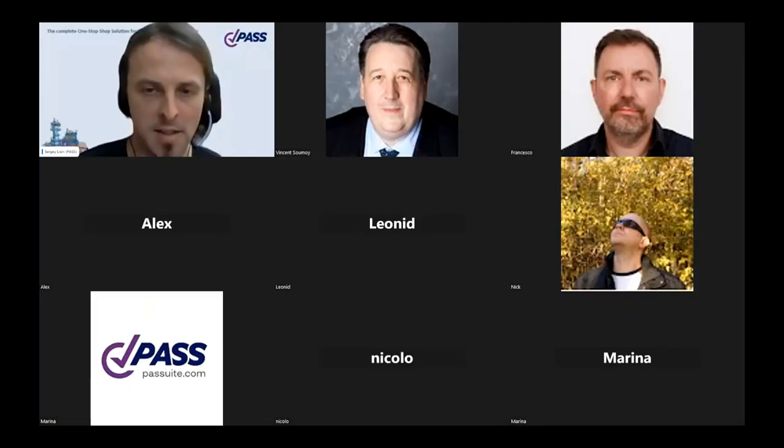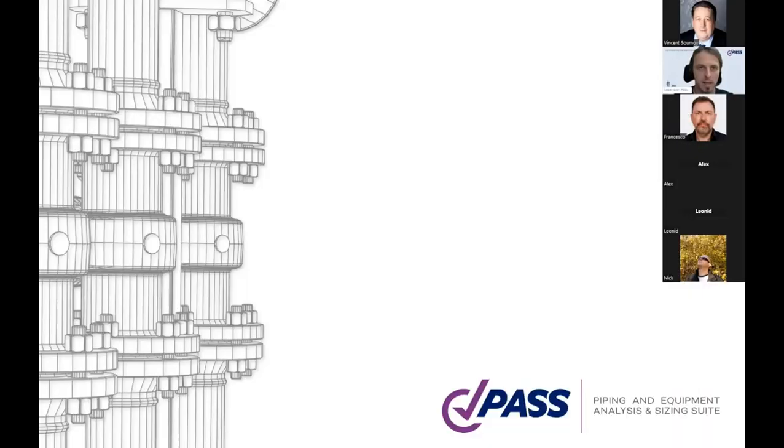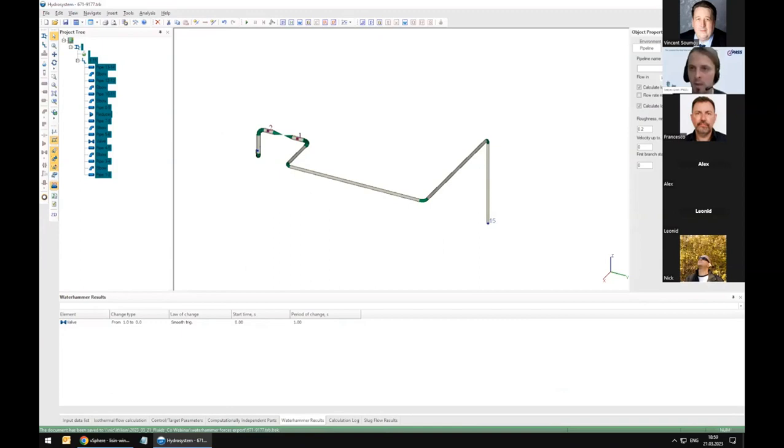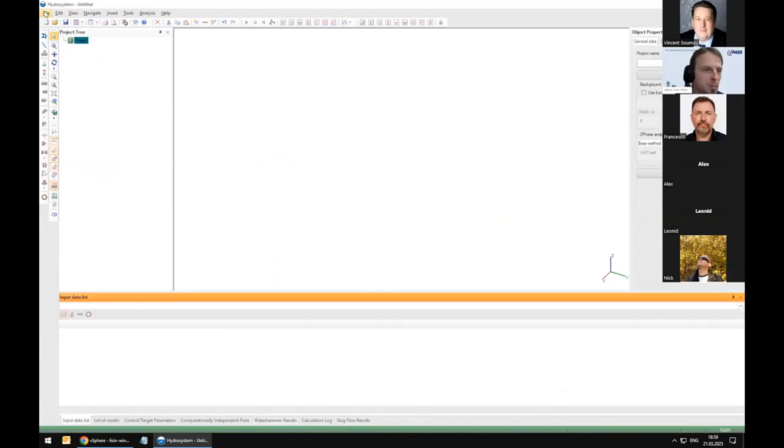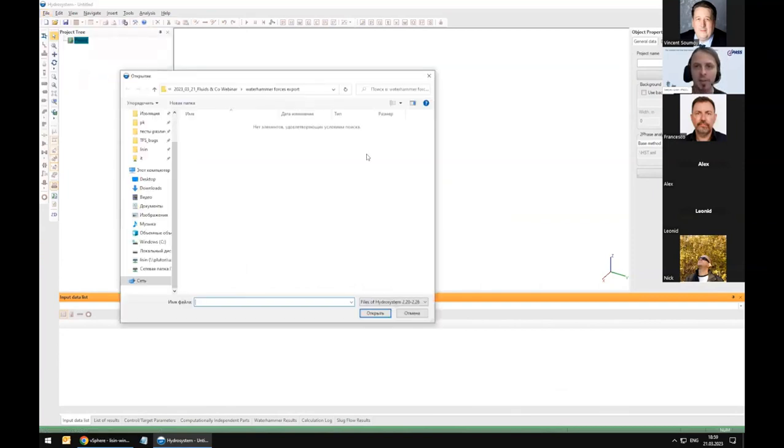Okay, thank you, Alex. Let's go back to PASS Hydrosystem. Water hammer is not the only harmful thing that can happen to your piping system. We also have problems with two-phase gas-liquid flow inside piping systems, because two-phase flow may cause different types of flow regime inside the piping system. And one of these flow regimes, or flow patterns as they call it in the literature, could be very harmful.